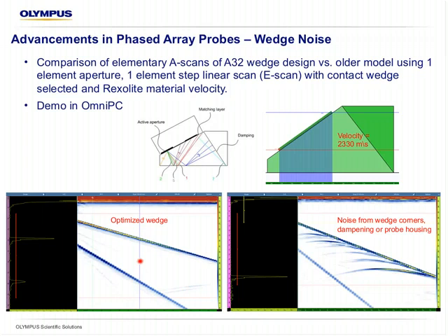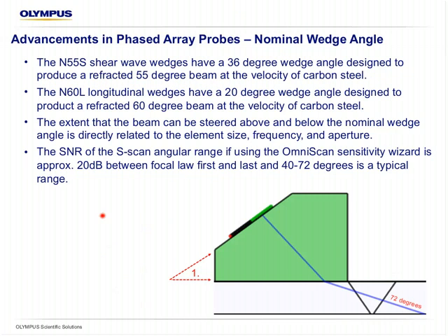In some other models, or using a configuration that pushes the limits of a wedge design, we can also see noise. This noise amounts to interference in our S-scan. Most customers don't have the reason to trace where it's coming from and why. It just interferes with the inspection. There's many different wedge echoes that can be eliminated or reduced, that we see in some configurations are directly impeding or interfering with the inspection. All of these, and what Olympus learned in the last 8 or 10 years of probe manufacturing, have been taken into account in the new Weld series.